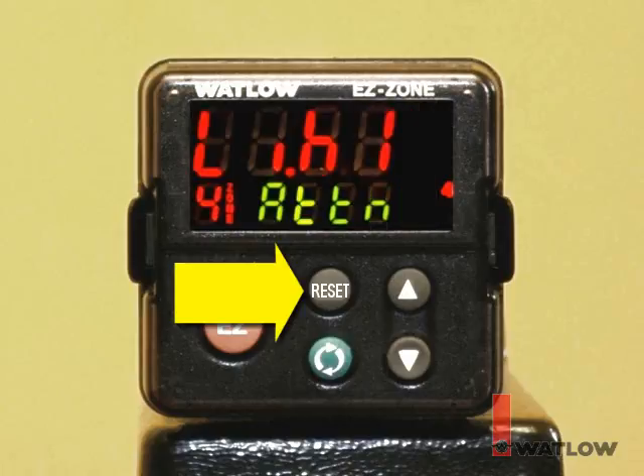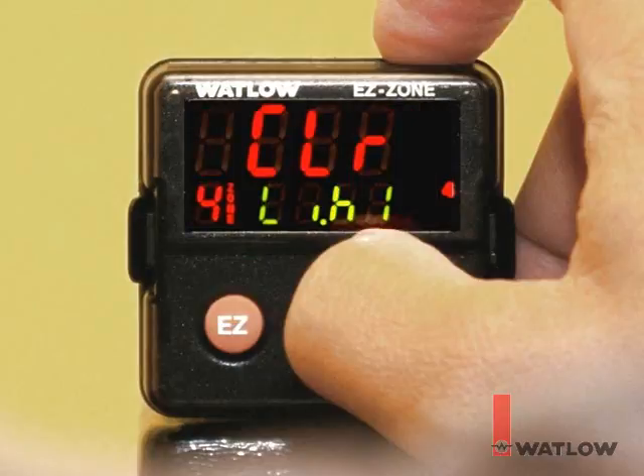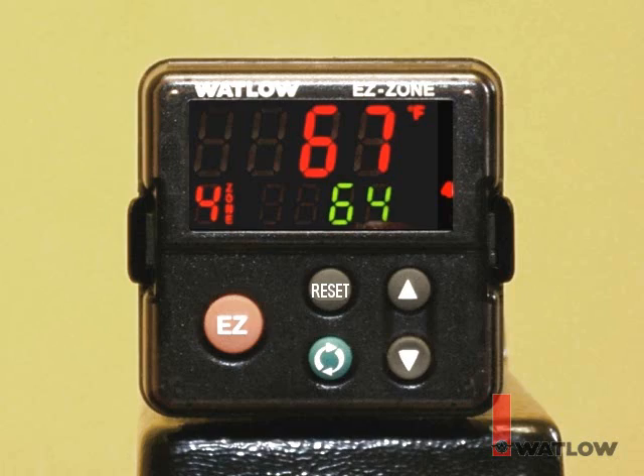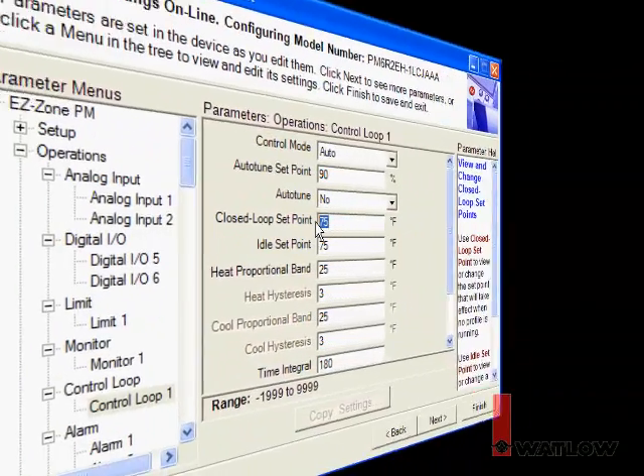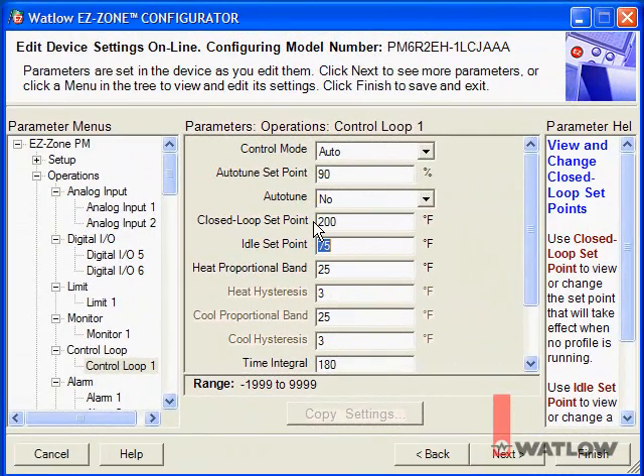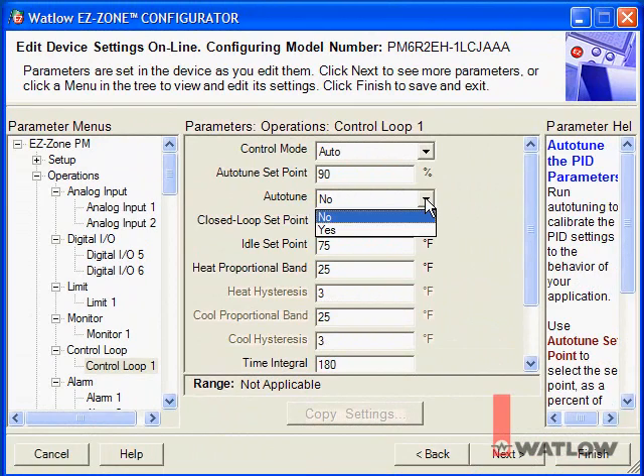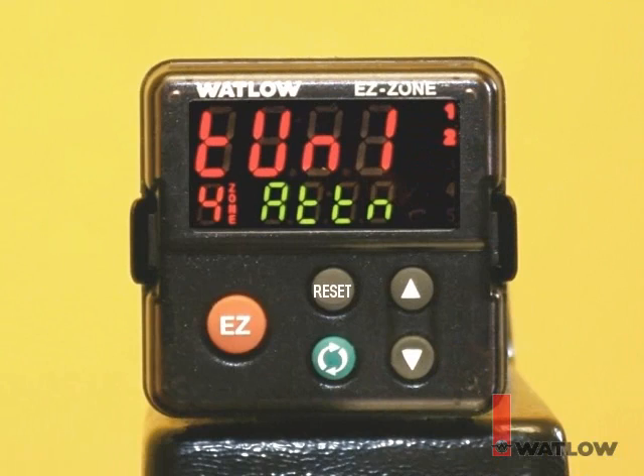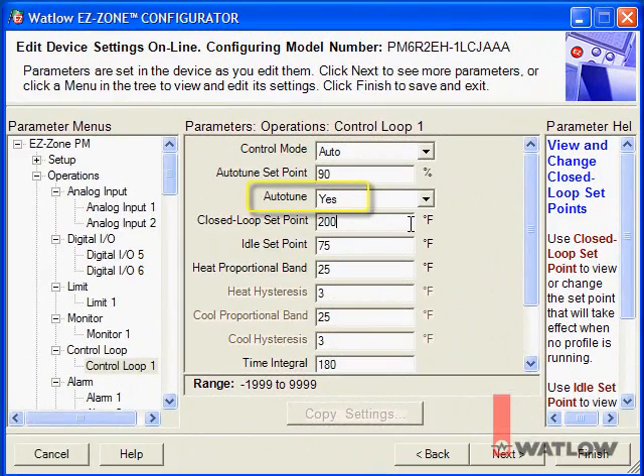Clear the limit alarm by pressing the reset or infinity key on the front panel. Now that the limit is reset, I can set the setpoint to 200 and start the controller's autotune. This will tune the controller for the heater and load. The controller display flashes 'tune,' and the autotune setting remains Yes while the controller is performing the autotune. The amount of time tuning takes depends on how fast the heater and load can heat up and cool down. Wait and allow the autotune to complete before proceeding.